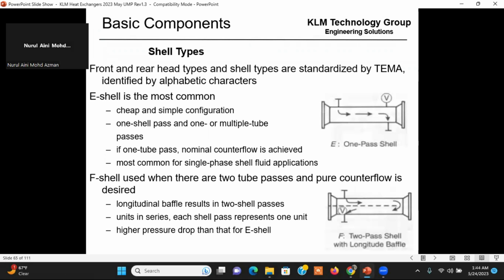Then they've got the middle section. All right. So they've got E, the most common. Typically, I tend to like an E. All right. So I'm going to use a B on the front end. I'm going to use an E on the second. It's most simple. It's common. It comes in and goes out. One pass shell. F shell is used when there's 2 passes and pure counterflow is needed. There's actually a baffle along the middle. It needs to be very clean service to have a baffle. And so it comes in here and it goes out that way. We'll talk about these baffles. And I want to be careful when I'm using baffles for fouling service.